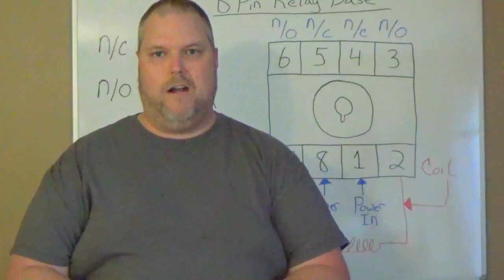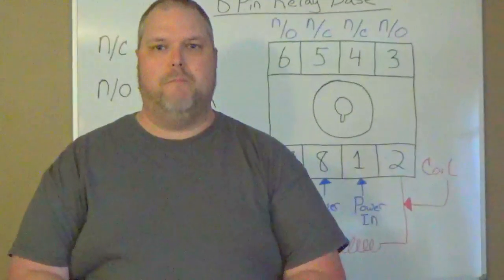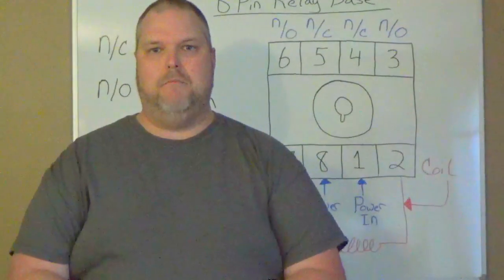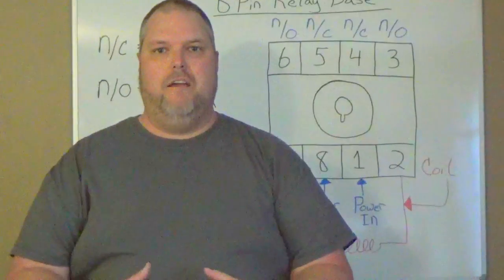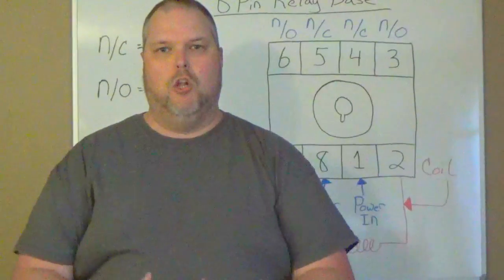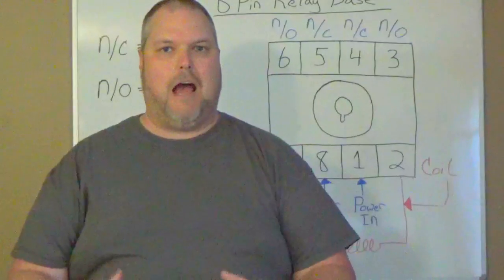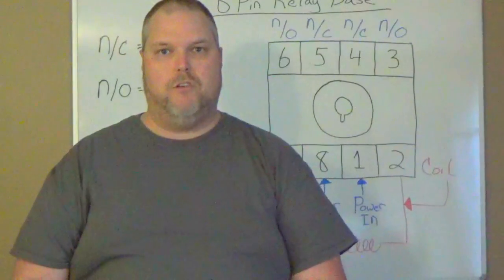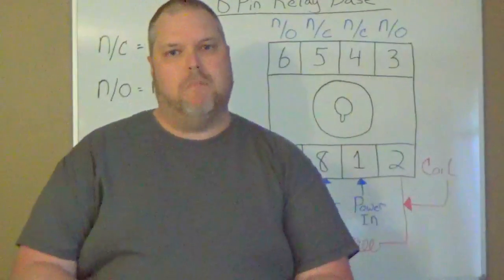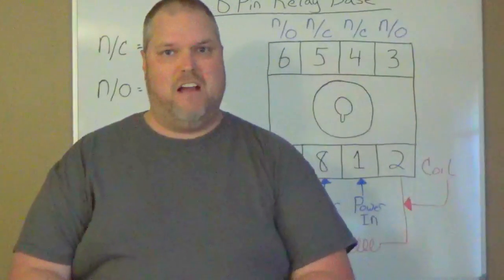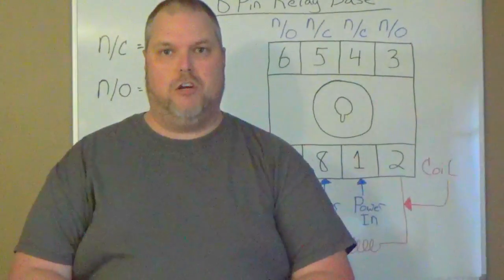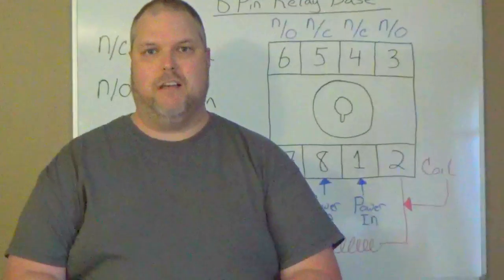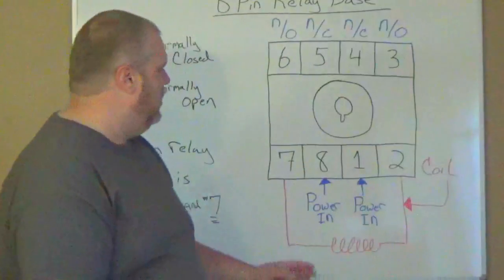I have not found a base that has been wired differently, but always remember to read the instructions. Anytime, especially when you're out in the field, if you get an 8-pin base, look at it and find out exactly how it's wired. The information in the package will tell you. I'm going to tell you 95% of the 8-pin bases you're going to receive in the field will have a setup just like this.